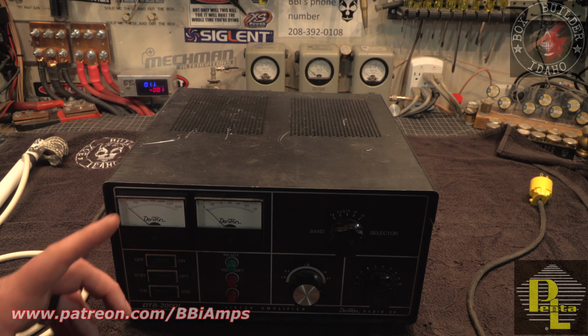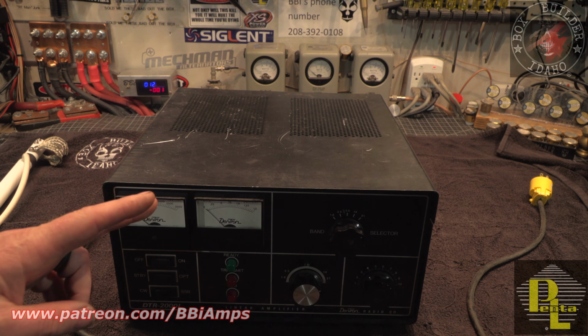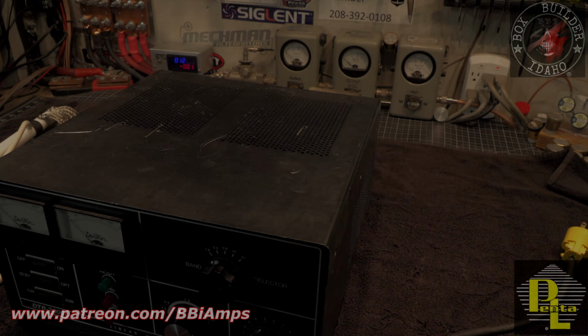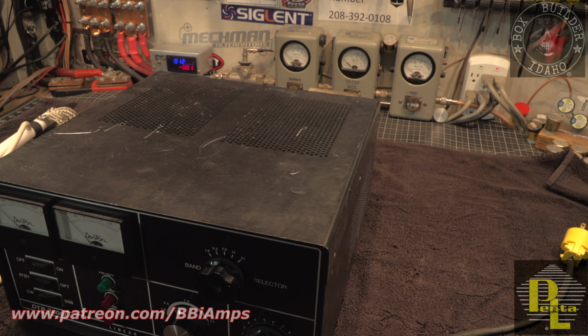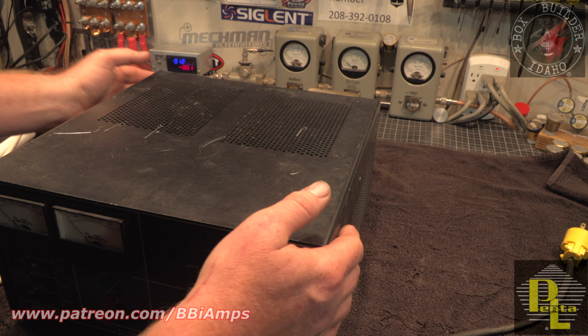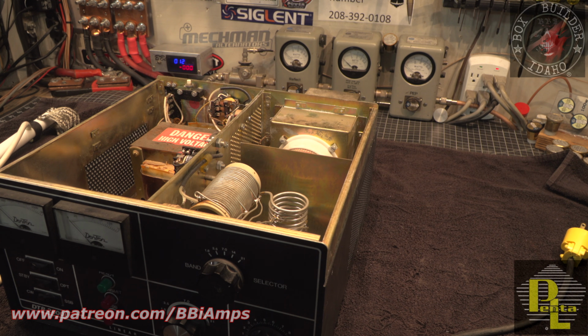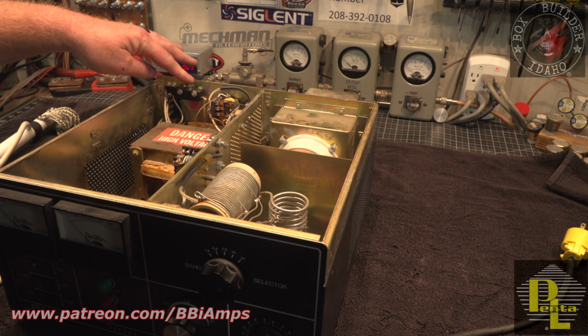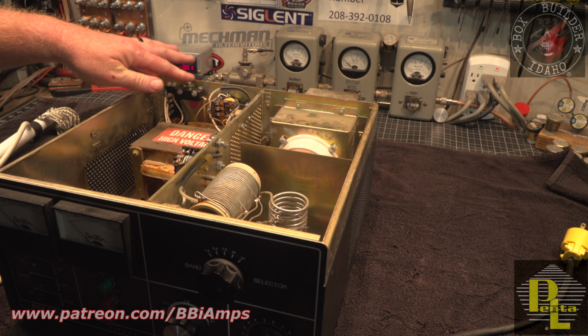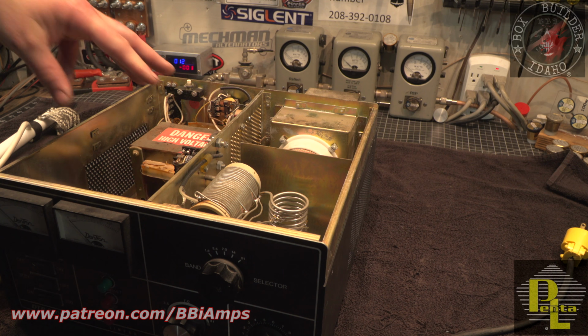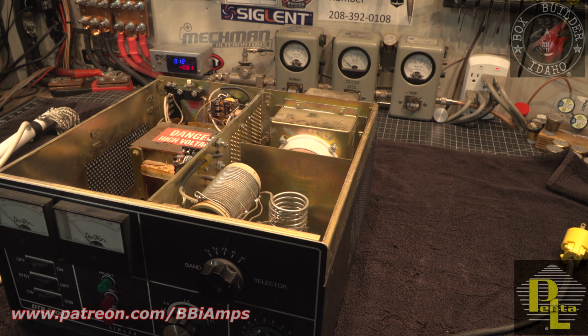Now, we do not trust this meter until we can verify what it's showing us is true. In most commercial built pieces of equipment that are sold by major corporations that have insurance and liability, there are certain safety standards that are built into all pieces of equipment like this. The Dentron, its safety switch is back here. If the cabinet is not on this thing, this switch allows the rest of this not to be energized, right? On Ten-Tec, they have a shorting bar. On some Ameritrons, they have a shorting bar. Ameritrons usually got dual interlocks.